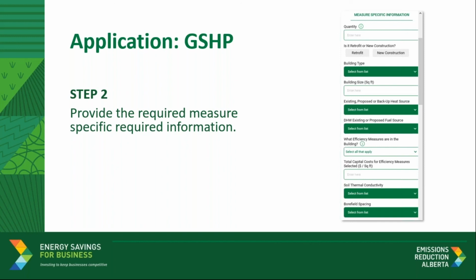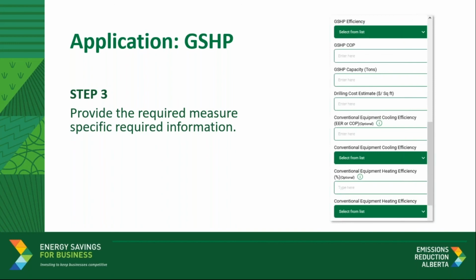You'll need to identify the soil thermal conductivity between two options and identify the bore field spacing. The next required field is the selection from a dropdown of the GSHP efficiency between low, medium, and high, then input the coefficient of performance of the system. The GSHP nameplate capacity in tons is required, and the estimated cost of drilling.